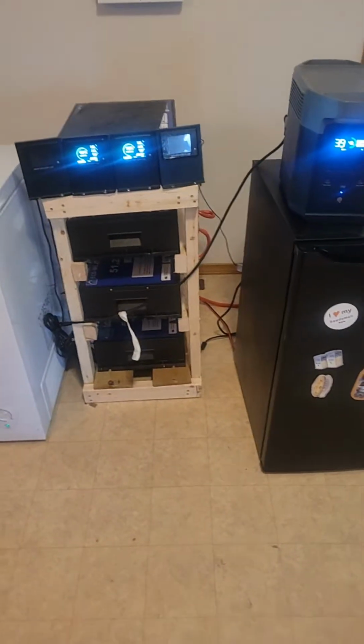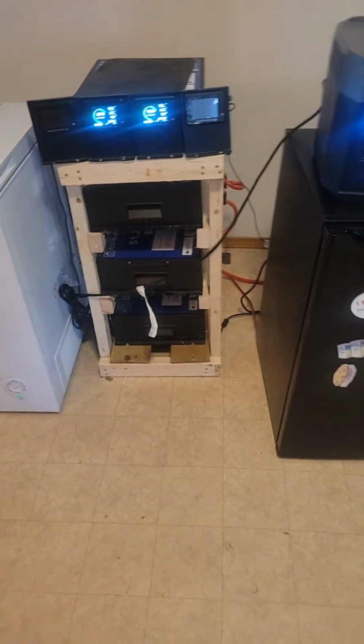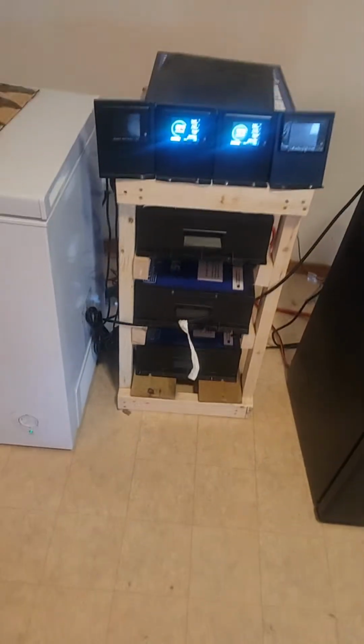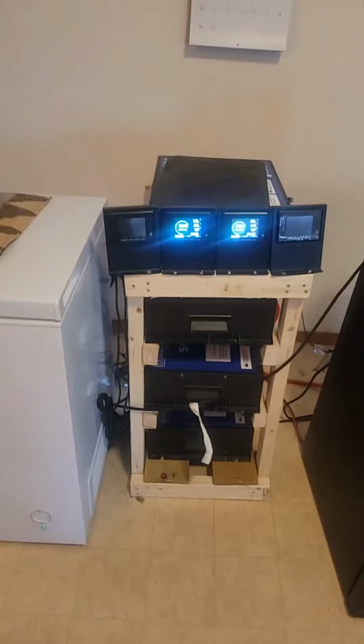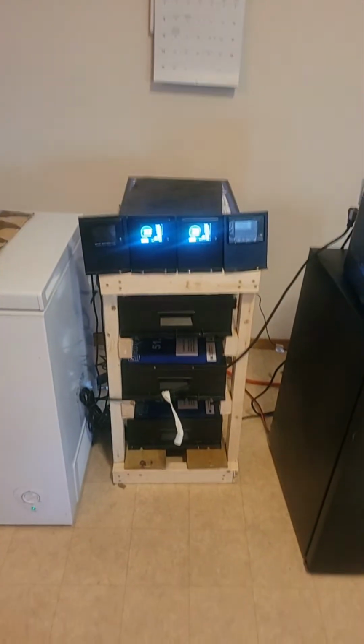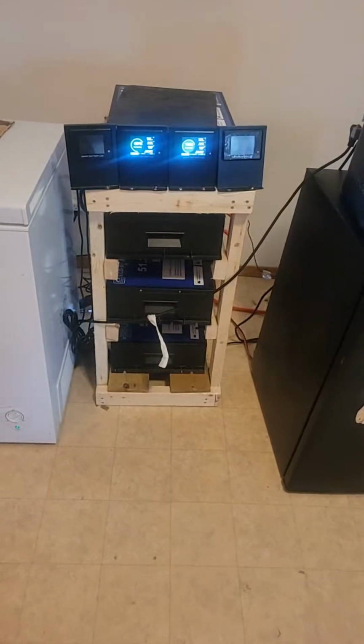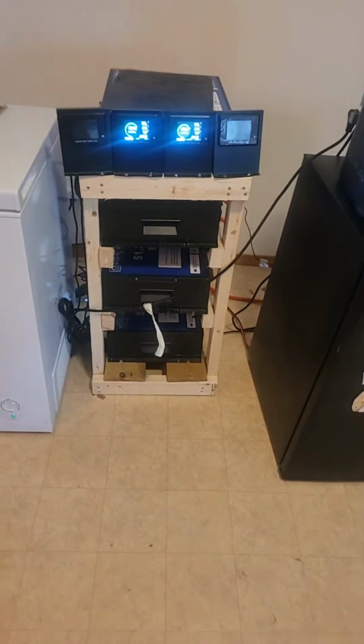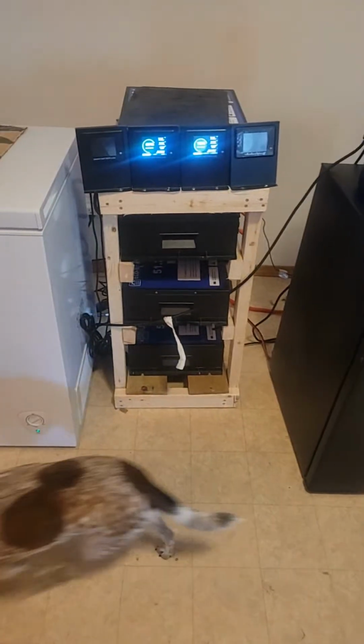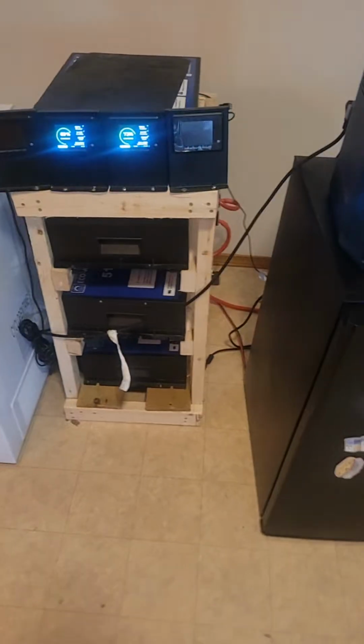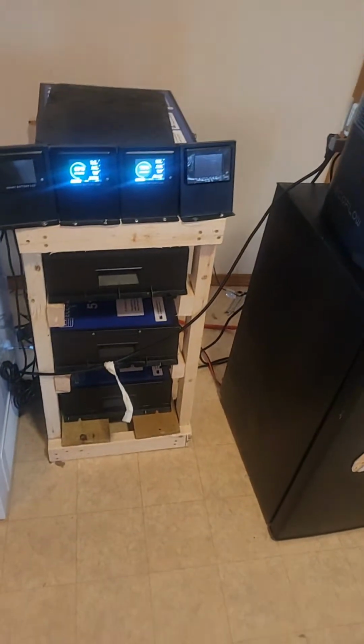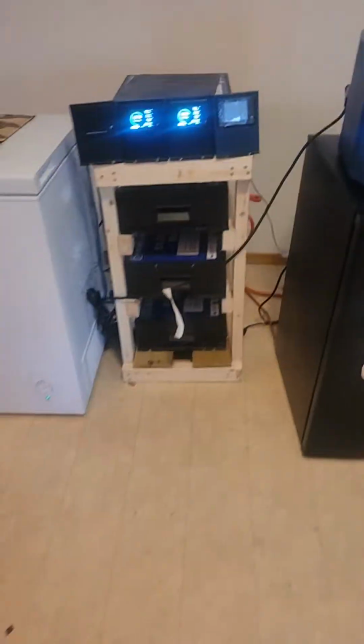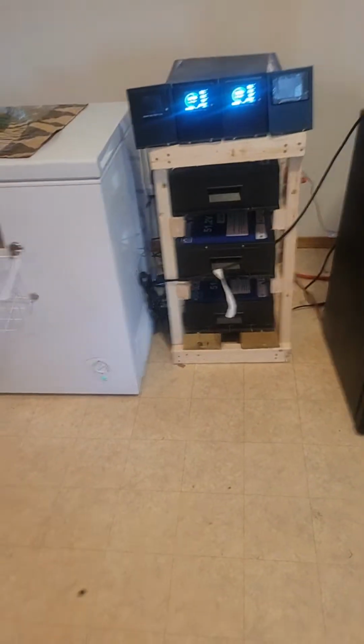If y'all ever got batteries wired together in parallel and have something similar happen, be sure to isolate the battery that has shut itself down. You can't just disconnect loads and charging from the battery bank itself, you actually have to disconnect that battery that shut down, that the BMS shut off, totally from the other two for that BMS to reset itself. And it did, within like 10 minutes. I'd sit around for 2 hours waiting for it to happen, but as soon as I isolated it completely, it was no time.